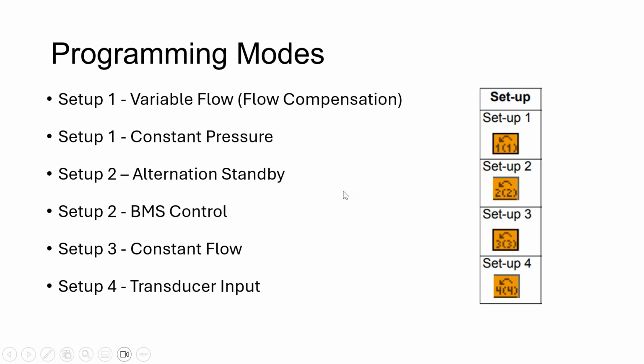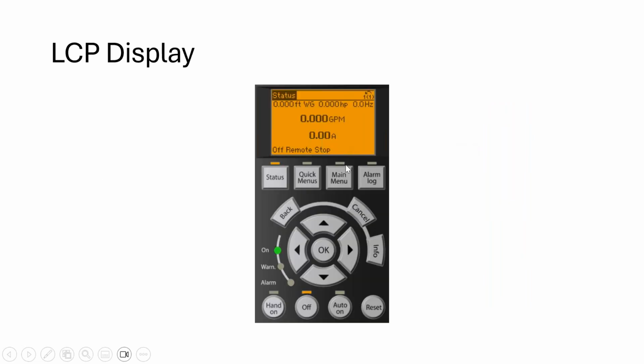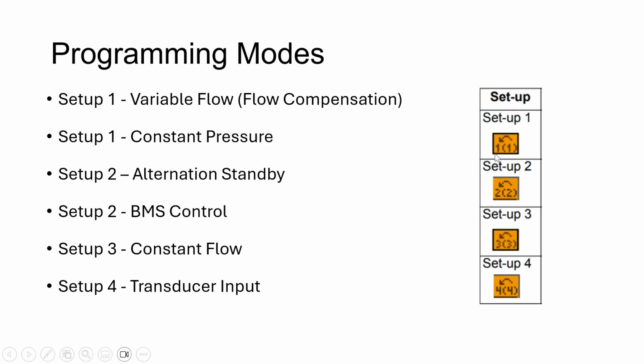So here are your different program modes. This is setup one, and that's how most systems work. That's variable flow, flow compensation, whatever you want to call it. That's the method that is very similar to accepting a signal from a remote sensor. If you think about it, that's how most pumps are run in the field, right? So flow compensation is setup one. Pretty straightforward. You set that up under the quick menu.